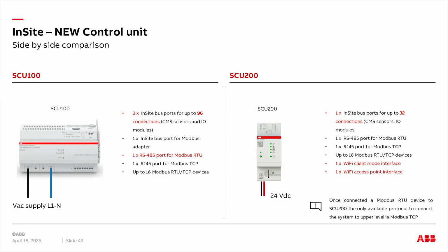The difference between the two is the SCU 100 is very much the all-in-one commercial, large commercial solution. It can give you 3 times 32 InSite bus ports, so that's up to 96 sensors or 96 MCBs you can pick up data from. It's got a Modbus RTU port, it's mains powered, and has a 3-phase meter built into it, so you can pick up the metering from your incoming supply as well on this device.